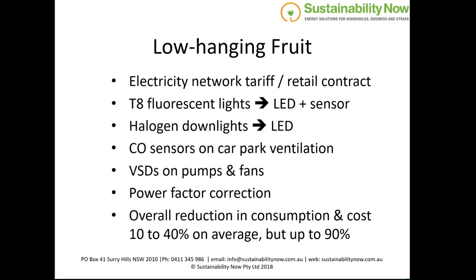As I mentioned before, putting carbon monoxide sensors on your car park ventilation system. So the Australian standard says that those car park ventilation fans need to run 24 hours a day, 7 days a week, unless you can show that the air quality in that car park is at a certain level. So it's very unusual that you do see a car park where those fans are running like that. Normally they're on a timer or they're switched off completely. But putting carbon monoxide sensors on there is a risk-based approach. So essentially the fans need only run when carbon monoxide levels reach 9 parts per million or more.